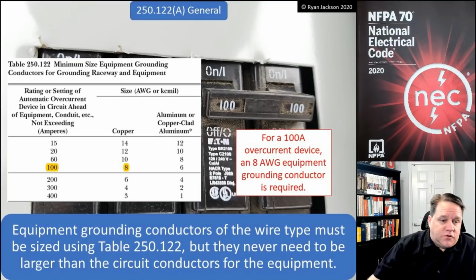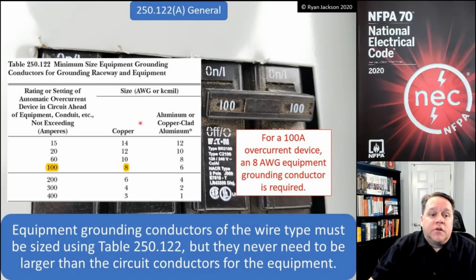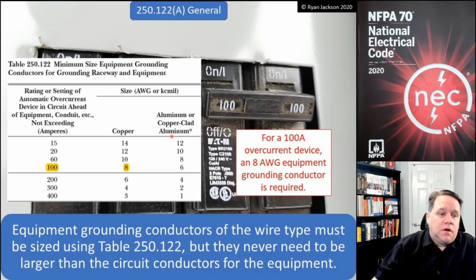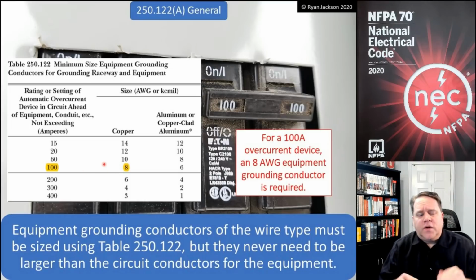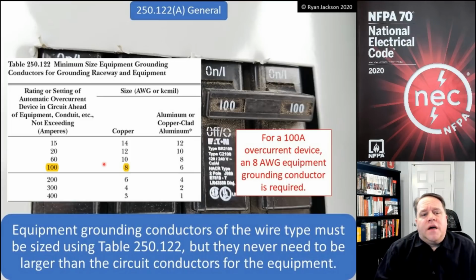If I have a 20 amp circuit breaker or fuse, then I would use a 12 gauge copper equipment grounding conductor. By the way, nothing against aluminum or copper clad aluminum. I'm just going to be talking in copper today. So if I have a 15 amp breaker or fuse, I use 14 gauge copper for my equipment ground. If I have a 30 through 60 amp circuit breaker, I would use 10 gauge copper.